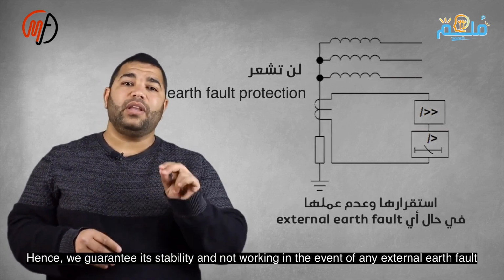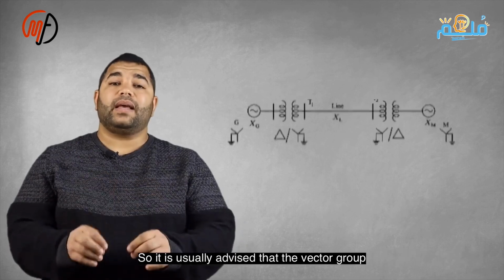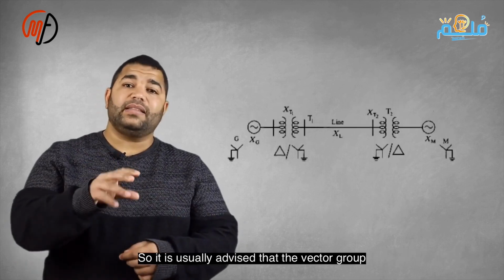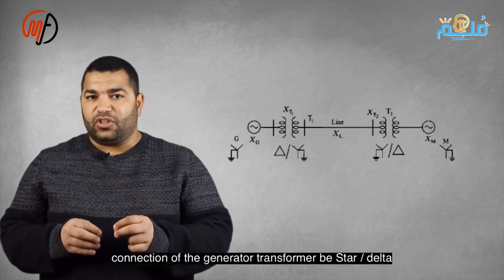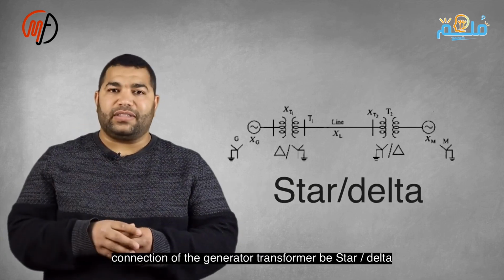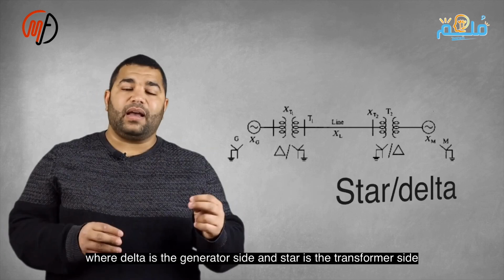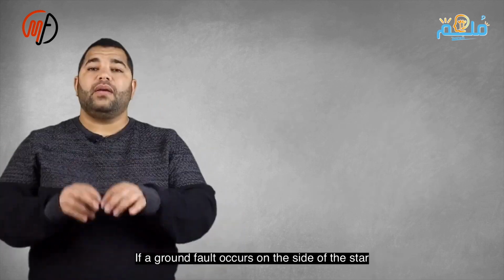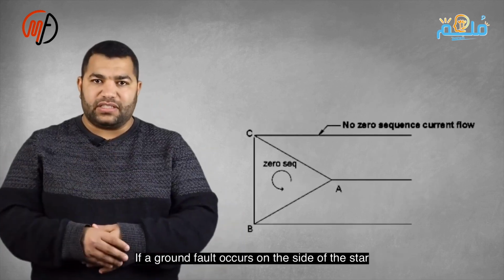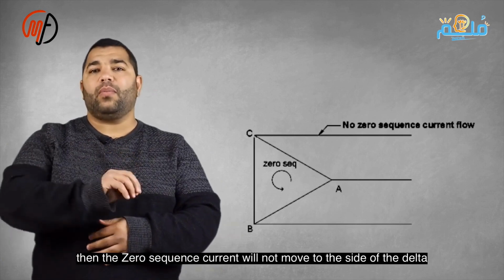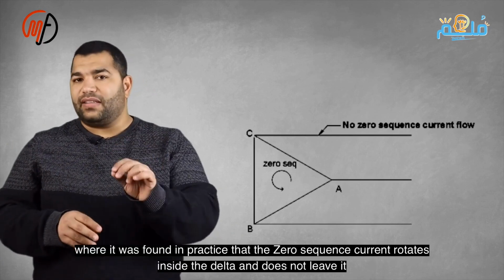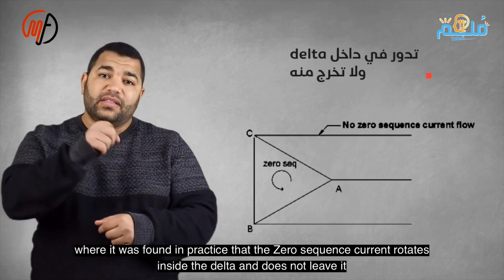The vector group for the generator transformer is typically star delta, with delta on the generator side and star on the line side. If a ground fault occurs on the star side, the zero sequence stays within the delta, not transferring out. Similarly, third harmonic currents causing overheating and overvoltage rotate inside the delta without exiting. Notably, there is no phase shift between red, yellow, and blue phases for the third harmonic, similar to the zero sequence current, with all vectors in phase.